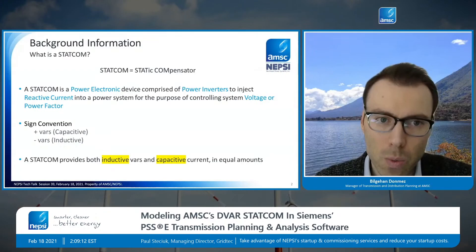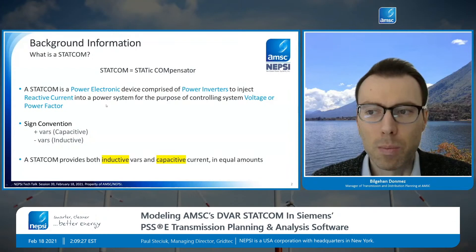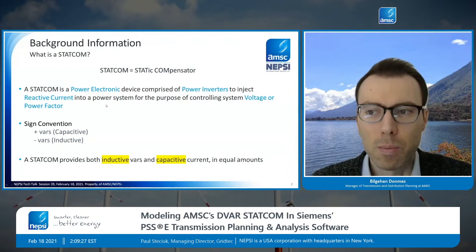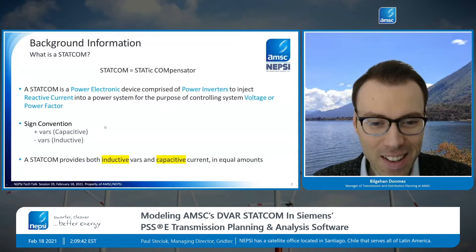Just quickly to go over what a STATCOM is: it's a power electronic device comprised of power inverters. Its purpose is to inject reactive current into a power system for controlling voltage or power factor. The sign convention is typically positive VARs is capacitive and negative VARs is inductive, though I do have a slide later where I'll change that convention.